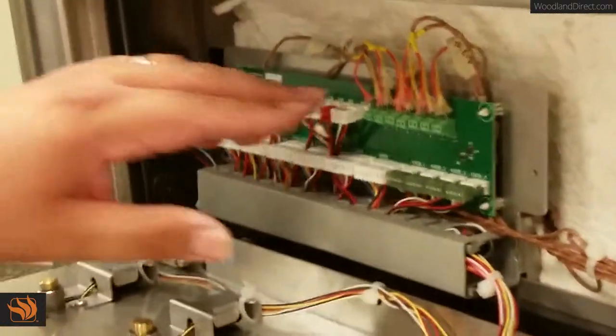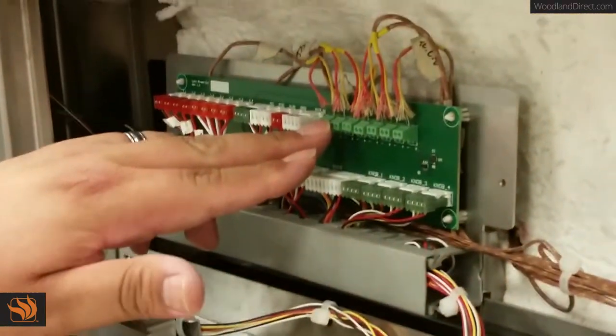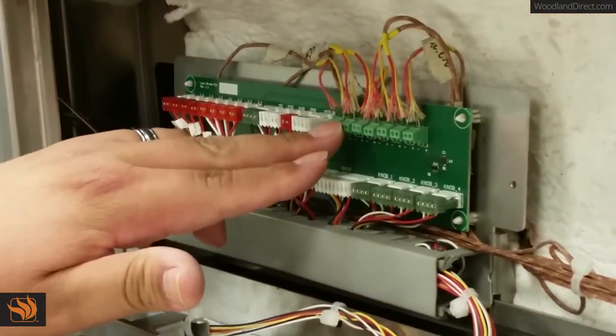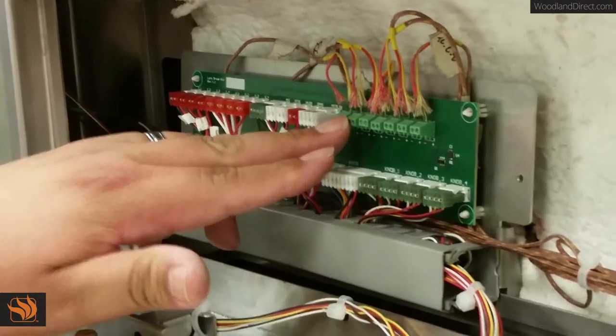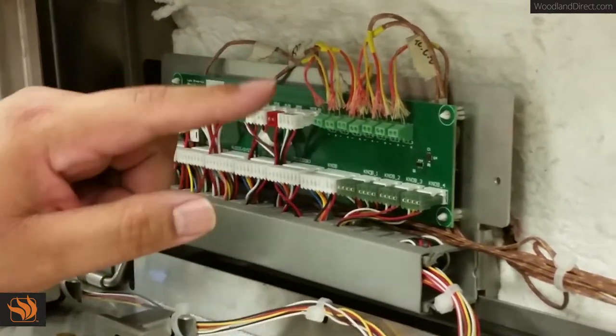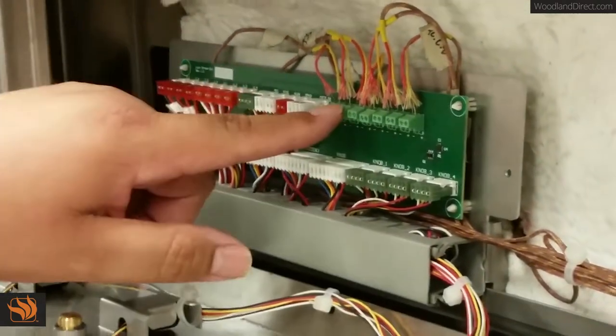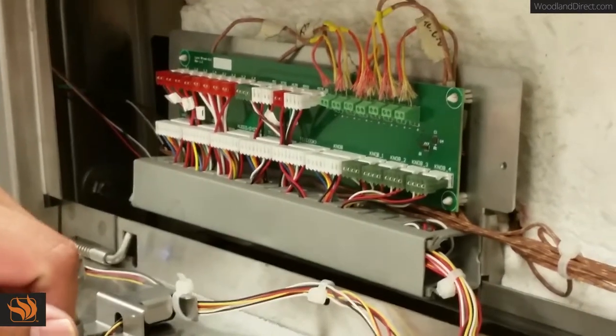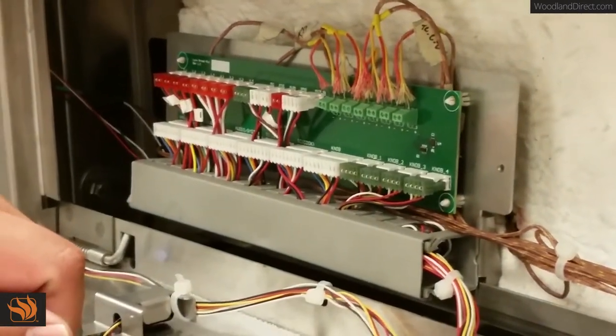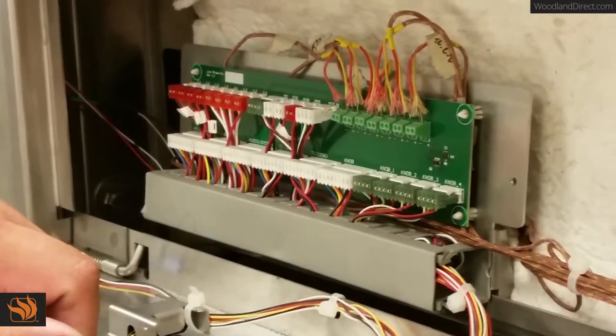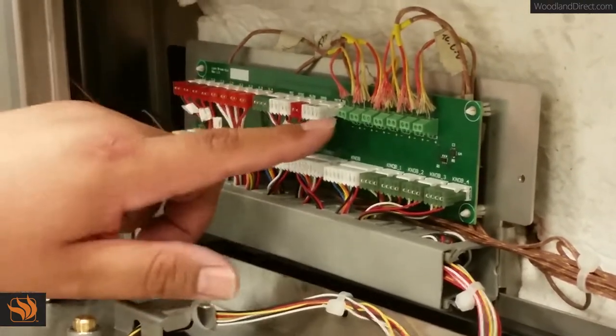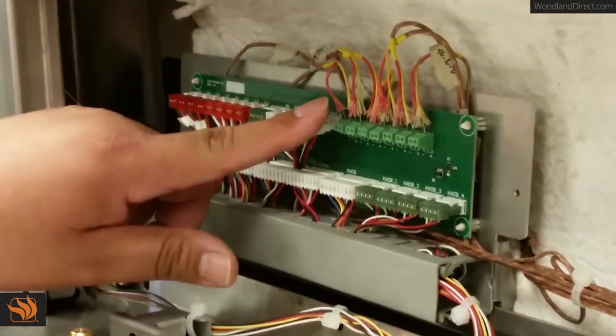In the event that the TCs have been disconnected from their mounting blocks, it will be hard to determine from this point which TC goes to which connection point. One way to find out is to apply the multimeter approach, connect each one individually, test the TC, and find out which is one, two, three and so forth.